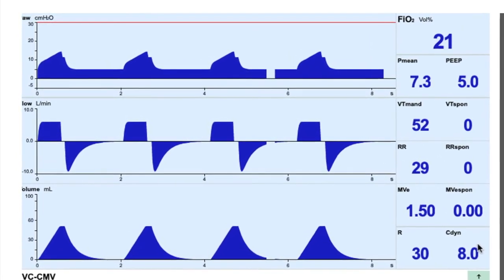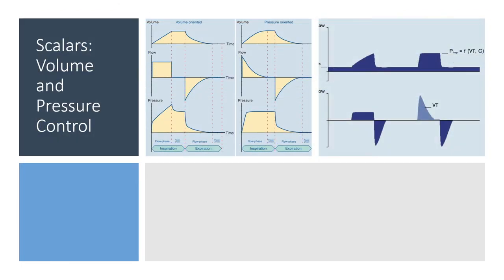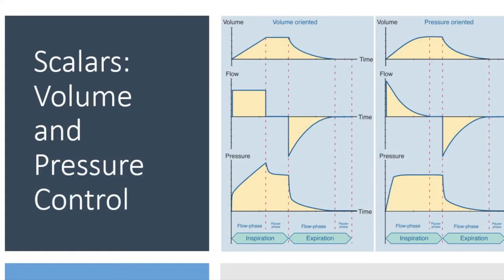These are the scalars you can expect to find on your ventilator: volume-time on top, flow-time in the middle, and pressure-time underneath. On the left are the volume control scalars, and on the right the pressure control scalars. Starting with the volume-oriented scalars and the most important one — flow — you have a constant flow, and then flow stops when the set target tidal volume has been delivered. Because the inspiratory time hasn't finished, you have a period of zero flow before cycling into expiration.